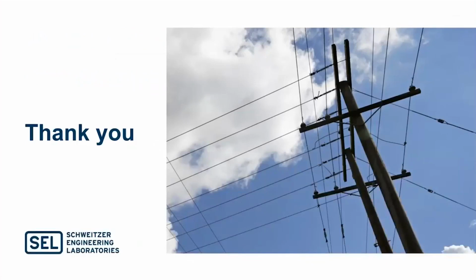Here's a good question. If Anthony is still on the line, can AST be used for a Delta system? So AST is only for application on solidly grounded power systems. We can use it on four-wire multi-grounded systems, or say a three-wire unigrounded system, but not on an ungrounded Delta or isolated neutral or impedance grounded system.